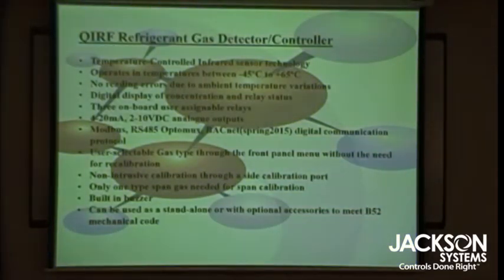The units come standard with a display, also 3 relays, RS-485. The biggest feature of this is that you can select the gas type. So let's say Jackson Controls here has 2 or 3 in stock, and you go to their counter and say, you know what, I need a refrigerant monitor for R507 and I need one for R22. All they have to do is take it out of stock, give it to you, or they can power it up for you and select the gas that you want to monitor. So you switch it to R22 or R507 or R134, and you're off and going. You don't even have to recalibrate it.